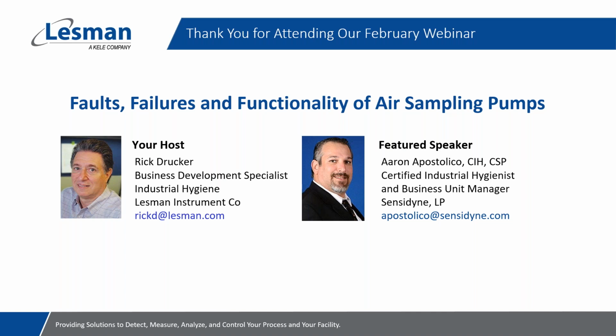Aaron, one question was, how does outside temperature and humidity impact the flow rates? Sure. So outside temperature can affect flow rates through the ideal gas law, which basically says the volume of air is proportional to the temperature and pressure. So if the temperature changes, it could cause a change in the flow rate.